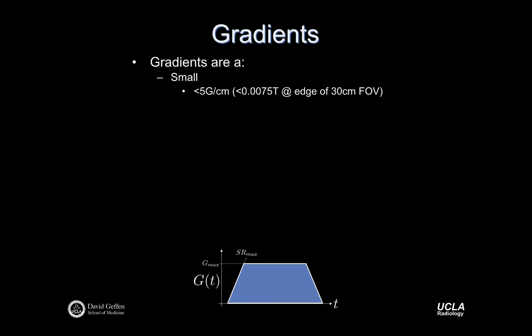So we've got B0 field strengths at 1.5 Tesla. We've got, what are B1 field strengths? Microtesla, right? So we go from Tesla to microtesla, and then gradients are in between, at millitesla, at least nominally millitesla. They're spatially varying. We talked about that a little bit already. And at least as we'll treat them in this class, they're linear, right? Now, every system has imperfections. I'll point to a couple today just so you have a heads up about it. But we'll treat them mathematically as being perfectly linear. So that certainly makes our life easy.